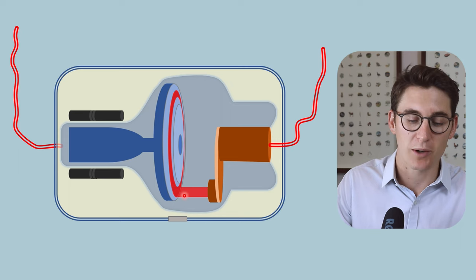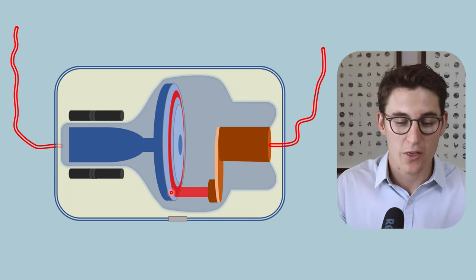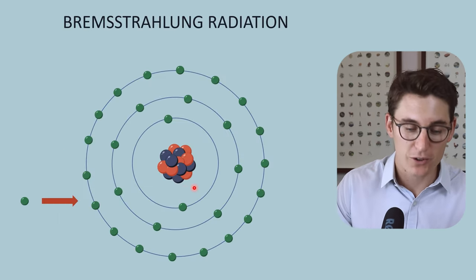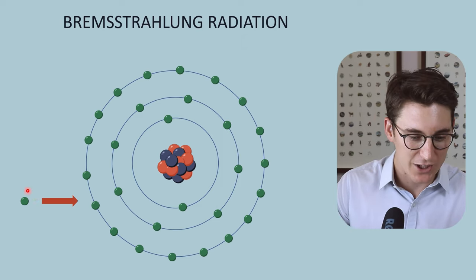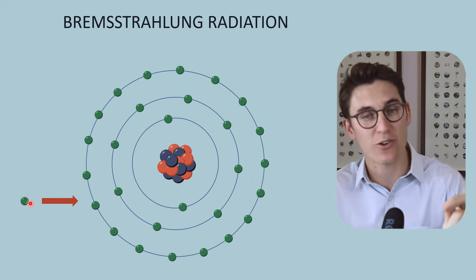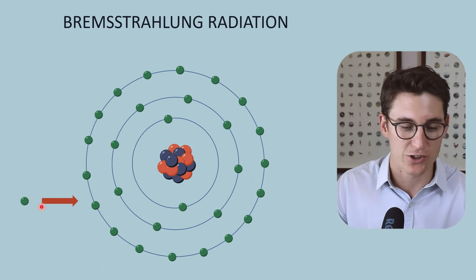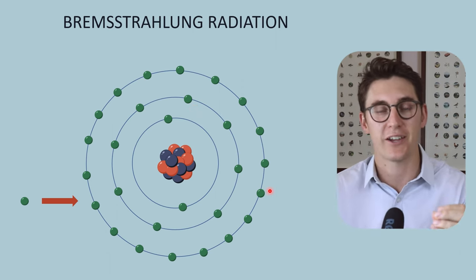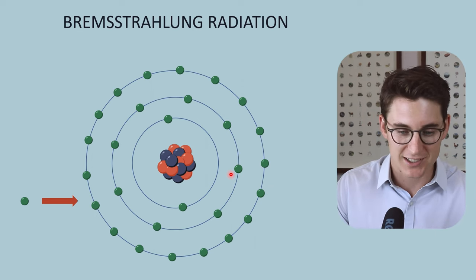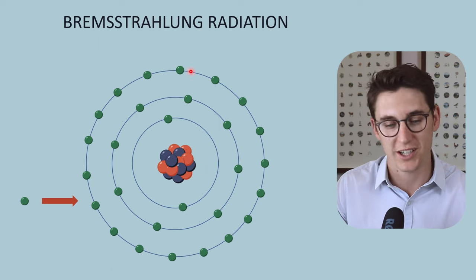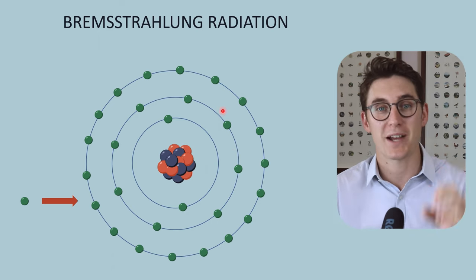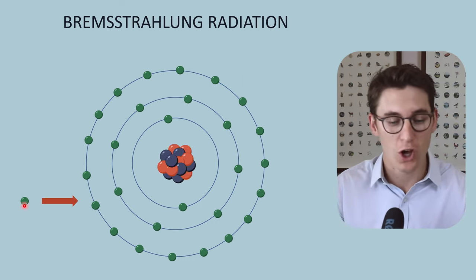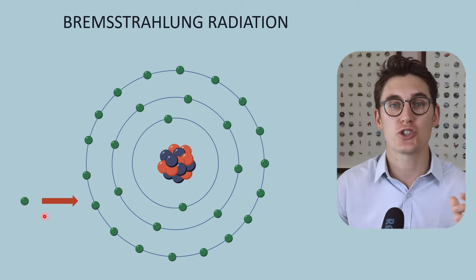Of that less than 1% that is converted into x-rays, the majority will be Bremsstrahlung radiation. If we look at our Rutherford-Bohr model of the atom, and we have an electron that has come from our cathode being accelerated towards our anode via our tube potential, it is going to strike our target material. This atom represents the target material of our anode, which is most commonly tungsten. This isn't technically a tungsten atom — there aren't 74 protons and 74 electrons here — but it's a diagrammatic representation of tungsten.